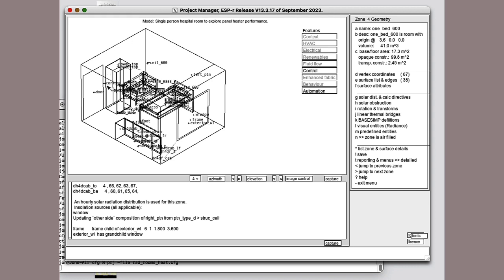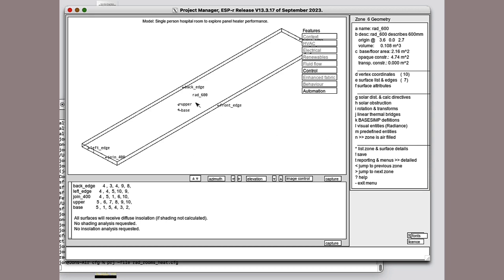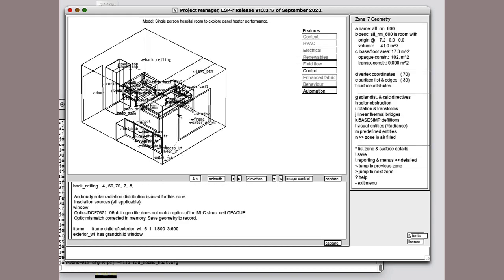Here's the middle one with a single panel running along the facade. Here's the heater for the first zone. What will be happening in here is that we've set a very high heat transfer coefficient so that any heat that's injected into this very thin zone immediately gets transferred to the heating surface. And the third room is identical to the middle one, except that the heater has been moved back slightly away from the facade.